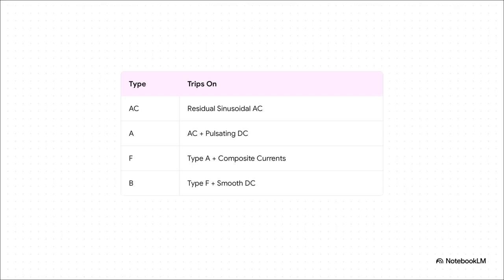In our modern world, not all RCDs are created equal. Your standard, old-school Type AC RCD is fine for simple circuits, but all our new electronics, washing machines, solar inverters, you name it, they can create weird DC leakage currents. And the scary part is, these can blind a standard RCD, so it just won't trip when you need it to. That's why we have these other types, A, F, and B, that are designed to see these more complex faults. Picking the wrong one isn't just a small error. It can make the RCD useless and give you a totally false sense of safety.